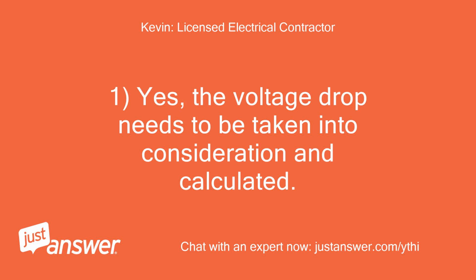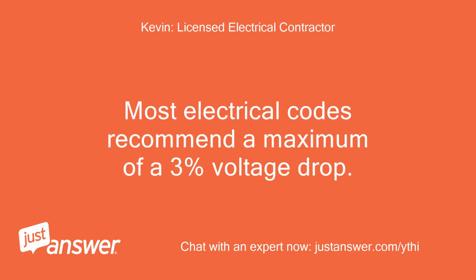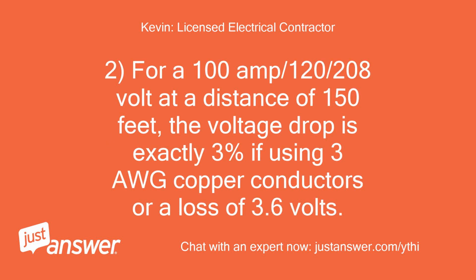1. Yes, the voltage drop needs to be taken into consideration and calculated. Most electrical codes recommend a maximum of a 3% voltage drop. 2. For a 100 amp, 120/208 volt feeder at a distance of 150 feet, the voltage drop is exactly 3% if using 3 AWG copper conductors, or a loss of 3.6 volts.